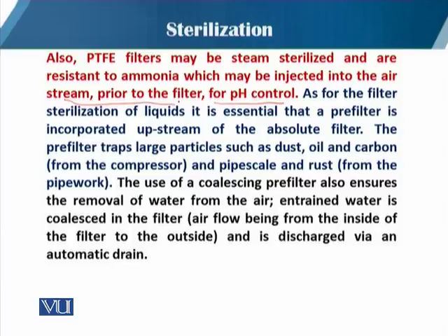As with the filter sterilization of liquid, it is essential that a pre-filter is incorporated upstream of the absolute filter. The pre-filter traps large particles such as dust, oil and carbon, that mostly come either from the air or from the compressor, and also pipe scale and rust. Because when there is some mechanical work, there will be some scaling and rust particles that can come along with the air.